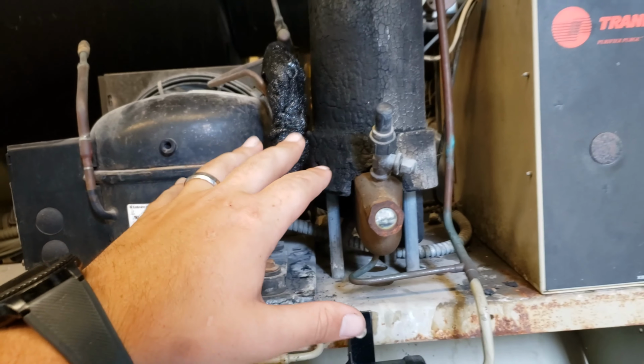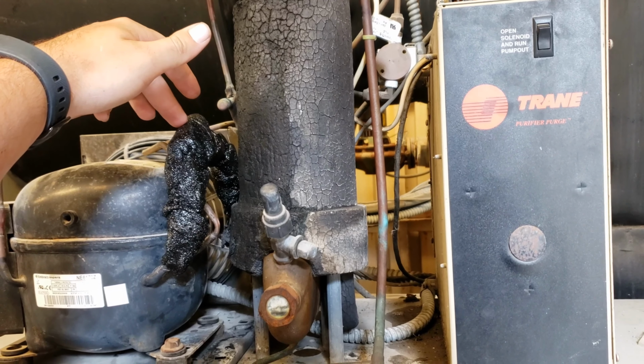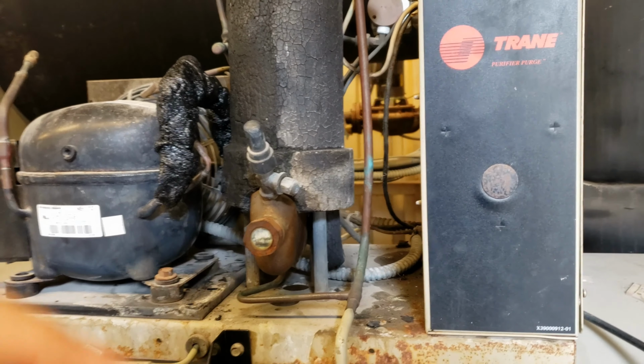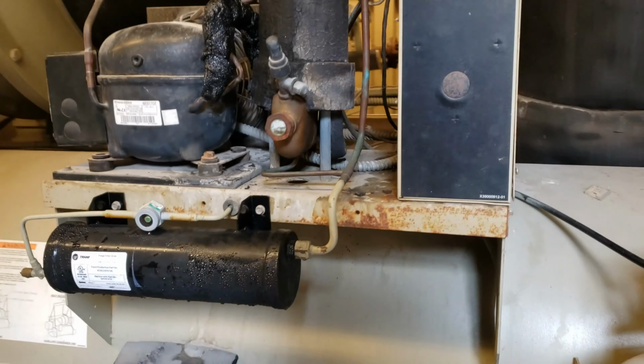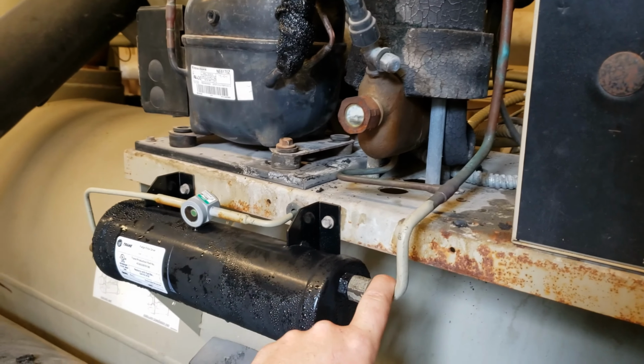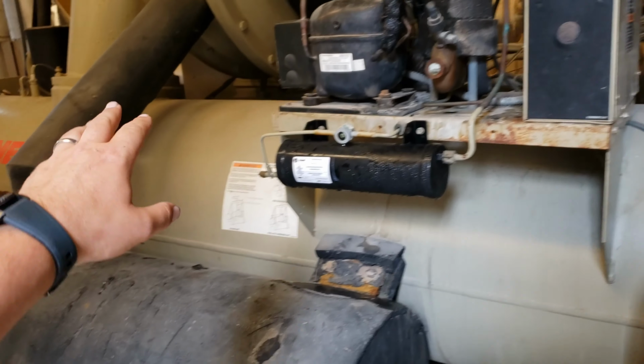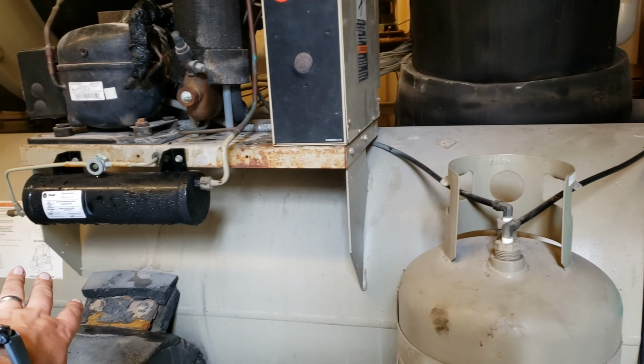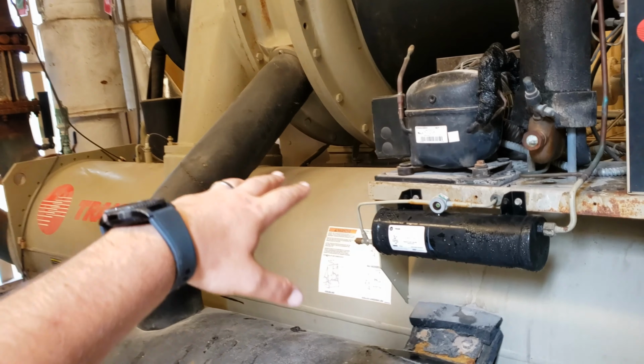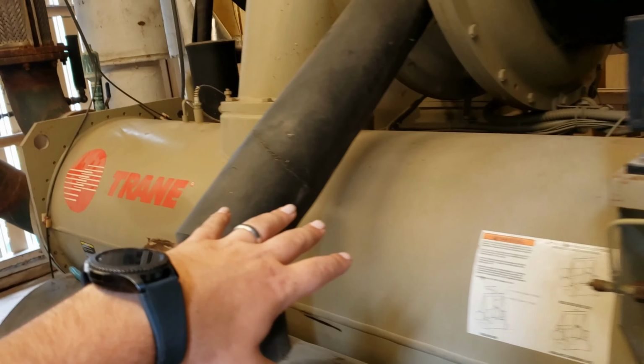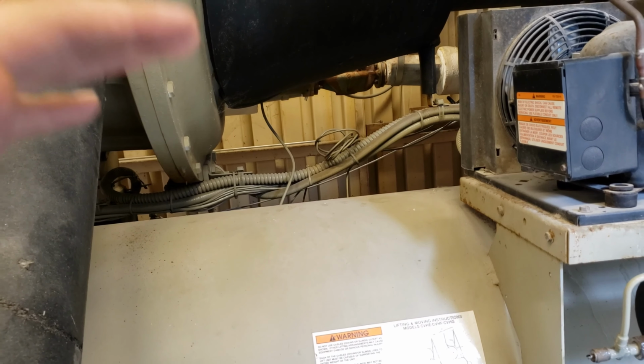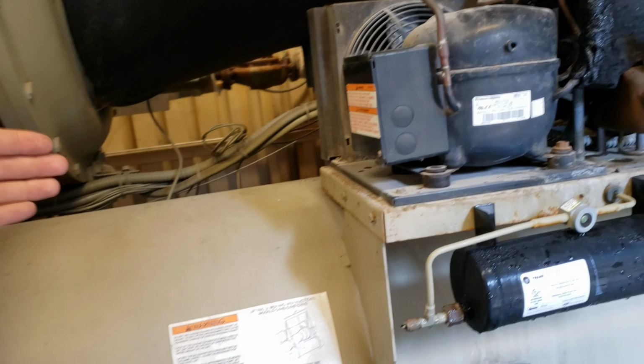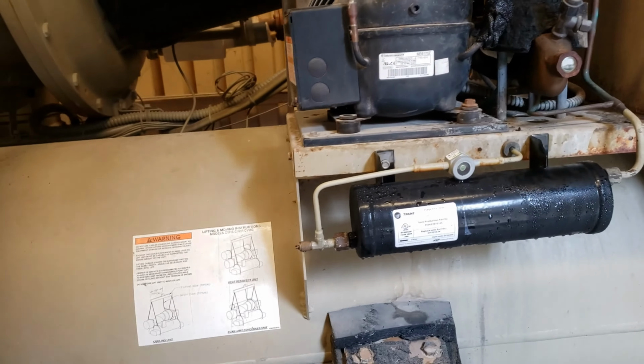So what this purge does is it's monitoring the suction temp here on the suction line, and then it has a liquid temp reference. Well, we don't have a physical liquid temperature sensor on this purge assembly, so what we're using instead is, when it's running, the condenser saturation, which is where that sensor really plays a big role.